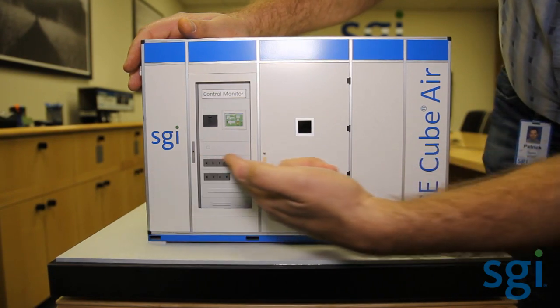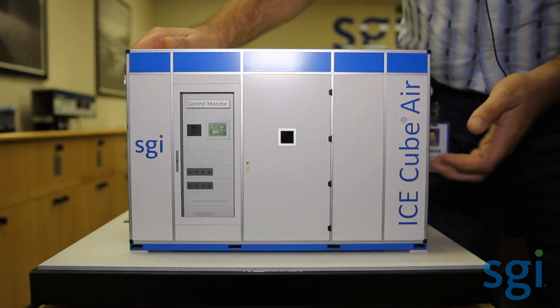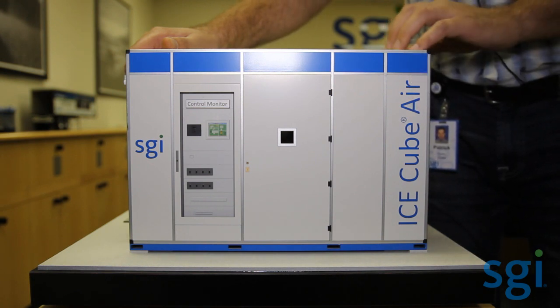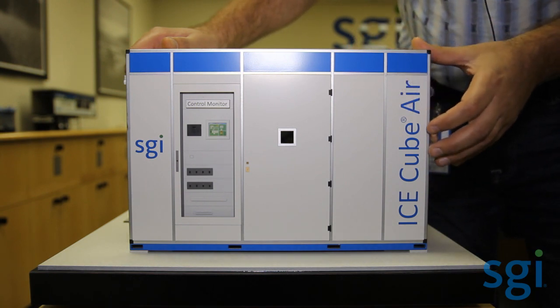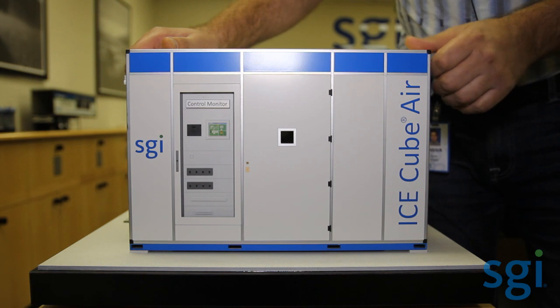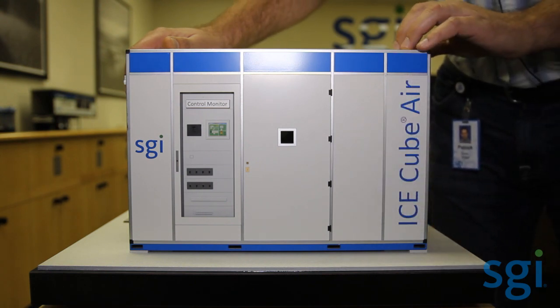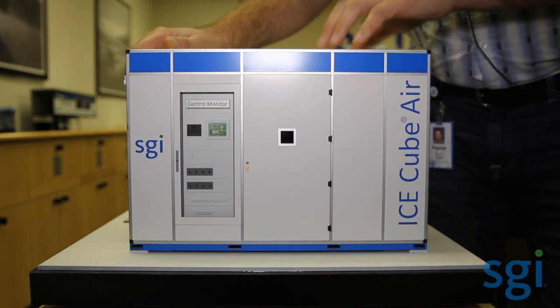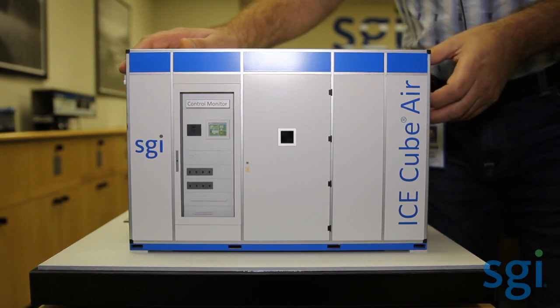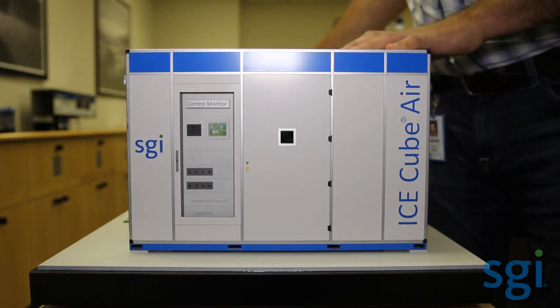We have the airflow going through the system from front to back. Off the shelf, four racks, 51RU or 52RU, and it can also support roll-in racks of 24 inches wide up to 89.25 inches in height. Standard SGI racks can roll right in, four of them. The unit has several options a customer can order, and it can be designed to order from the ground up. It's expandable — this particular unit expands out and has three expansion units that total 16 racks.